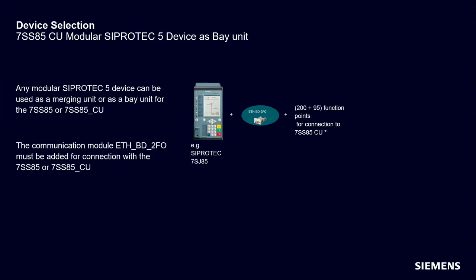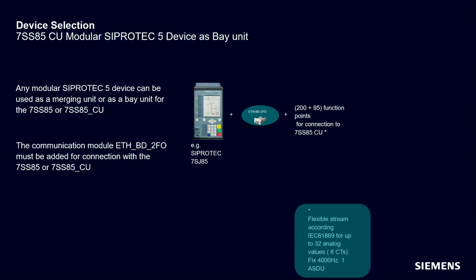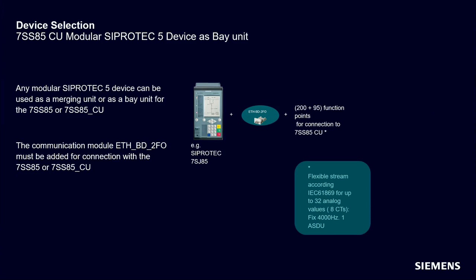So all in all, to use a 7SJ85, a 7SL, a 7SD, a 7UD or whatever is available as a bay unit for distributed busbar protection, you have to add the communication module and you have to add 295 function points. Also in this case, it's the same: you can use it for up to 8 current transformers, up to 8 bays for communication.